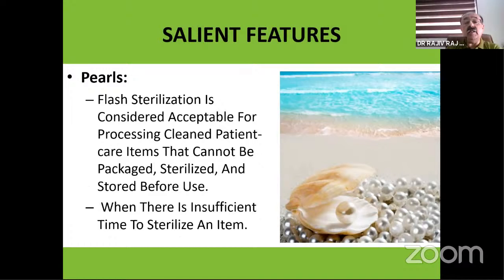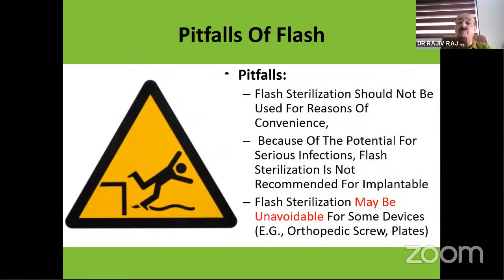Now, it cannot be used in a package or stored before use. So that's one aspect of it. And it is only to be used when there is insufficient time to sterilize an item. One must avoid using implants which have been flashed inserted into the body. It is not recommended that implants be flashed.